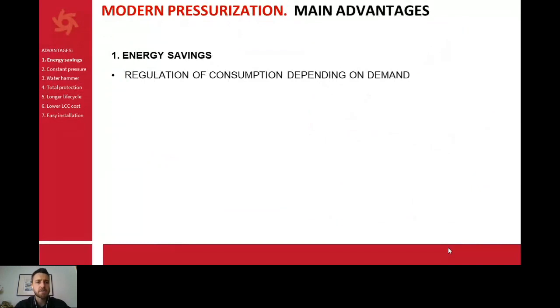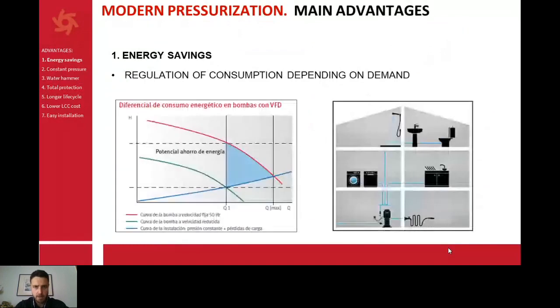Why do we have energy savings? Because of the regulation of the consumption depending on demand. In the old systems, whether you have one shower or two or ten, the demand is different, but you always have the maximum power consumption. This is why modern pressurization is so important, because we can adapt the power consumption to the demand. If we have less demand, we spend less power. So this is very important, and it gives the booster set more efficiency. That's why it's so important.